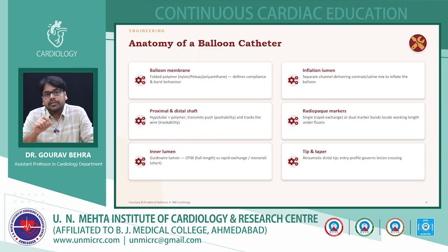There are different parameters. The inner lumen is where the guide wire passes through the balloon. The inflation lumen is a separate channel delivering the contrast mix to inflate the balloon. Then the radio-opaque markers that are present within the balloon, and the tapering tip, which is atraumatic.